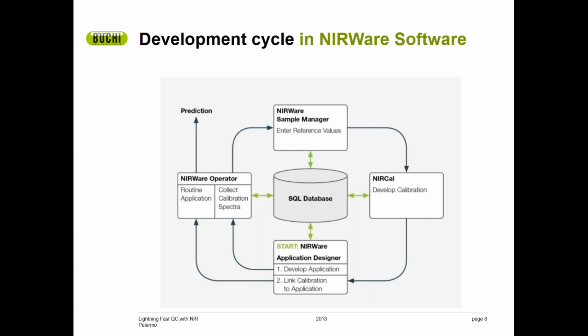This is what the application development cycle looks like in our NIRware software. We have three unique modules: NIRware Management Console, NIRware Operator, and NIRCal, which interact with the Microsoft SQL database. NIRware Management Console is where applications are created, spectral properties and results are managed, and where security settings are defined, among other administrative tools. NIRware Operator is used to operate the instrumentation. NIRCal is the chemometric software used to create and/or test calibration models. Once a calibration is developed, it is appended to an application for routine use in the operator software.